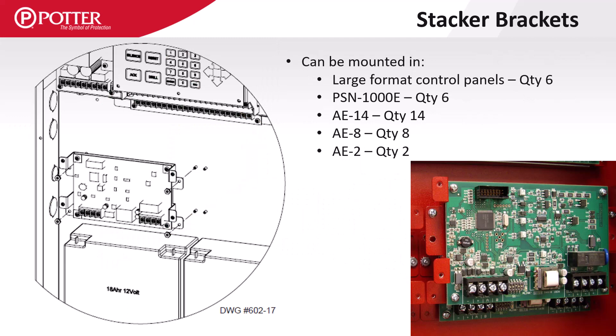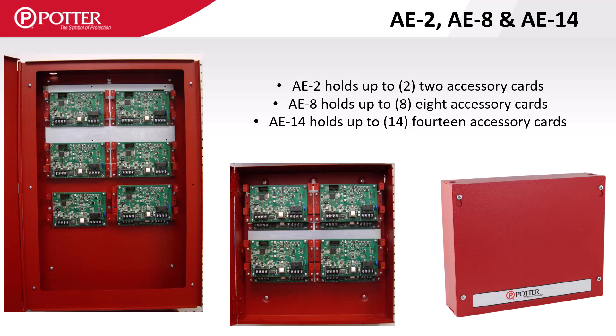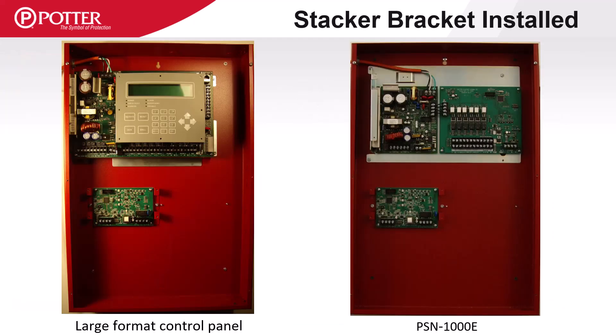The stacker bracket cards can be installed in large format control panels, the PSN-1000E power supply, and in AE P-Link module expansion enclosures. There are several accessory card enclosures available for mounting P-Link accessory cards: the AE-14 can house a total of 14 P-Link cards, the AE-8 can house eight, and the AE-2 holds two cards. The large format panels and PSN-1000E enclosures can both hold six stacker bracket accessory cards by installing them two side-by-side and three deep.